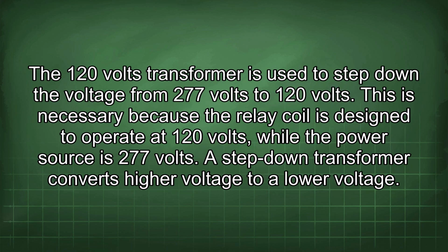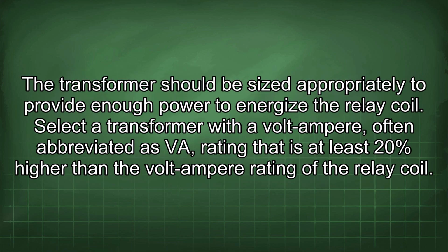The 120 volts transformer is used to step down the voltage from 277 volts to 120 volts. This is necessary because the relay coil is designed to operate at 120 volts, while the power source is 277 volts. A step-down transformer converts higher voltage to a low voltage. The transformer should be sized appropriately to provide enough power to energize the relay coil. Select a transformer with a volt-ampere, often abbreviated as VA, rating that is at least 20% higher than the volt-ampere rating of the relay coil.